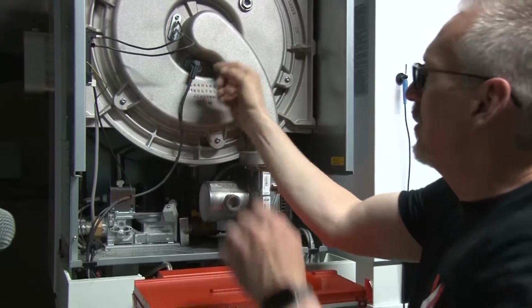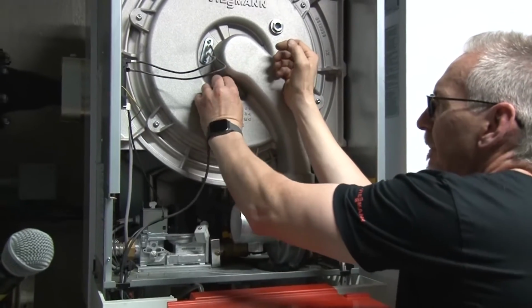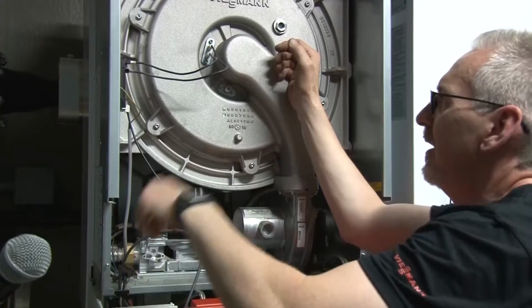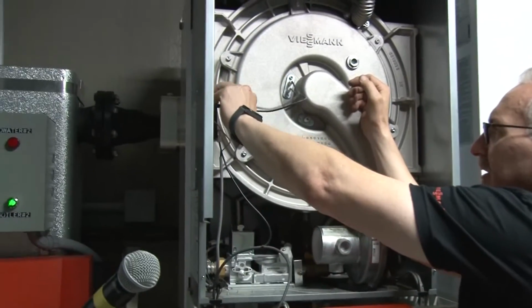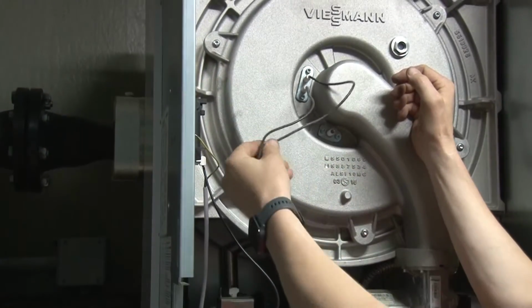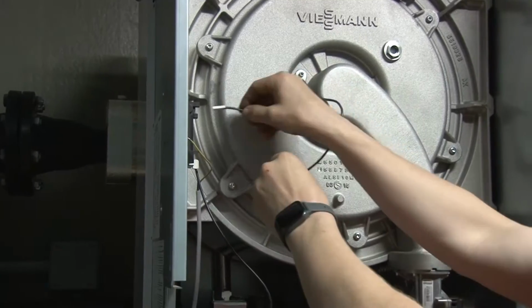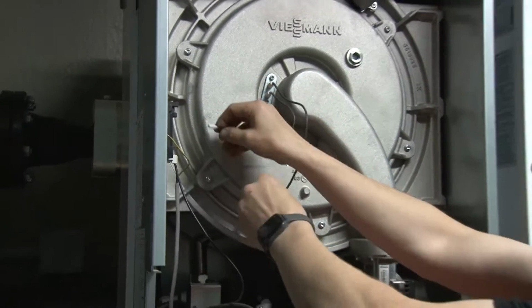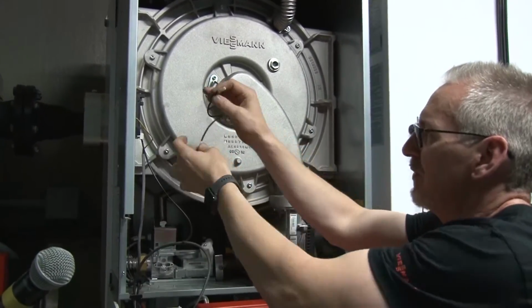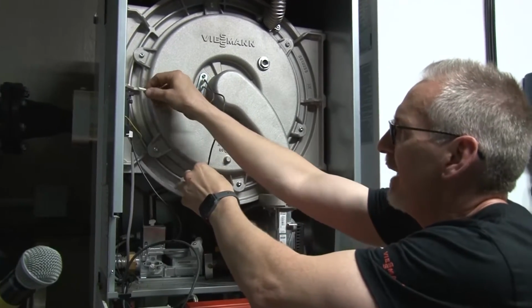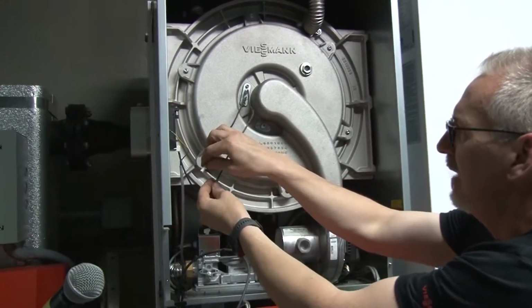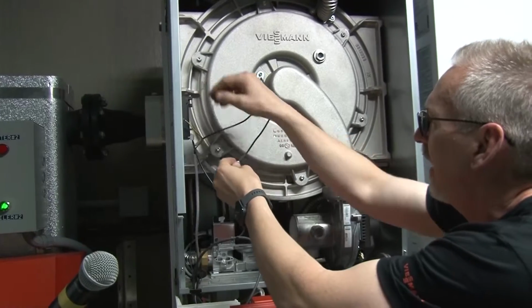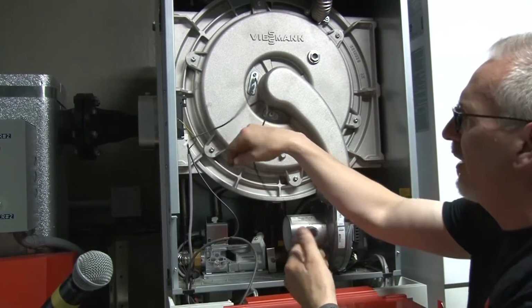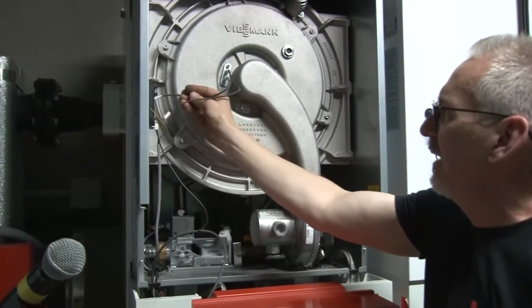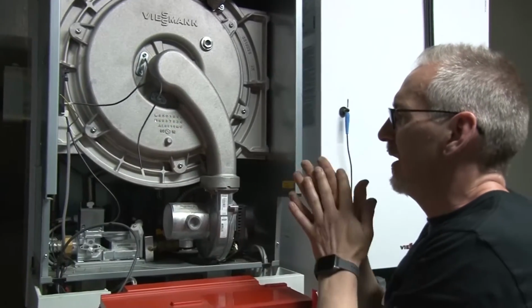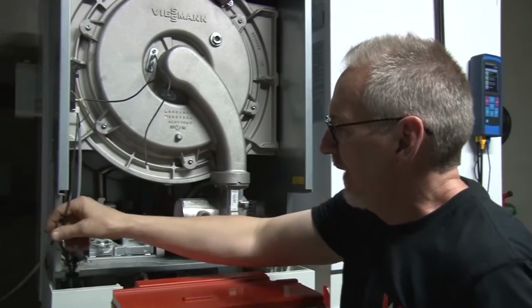I need to also remove my ionization electrode, and that's sitting right here, as well as the ignition electrodes. And the ignition electrodes, there really doesn't matter which way you put these back in. So if you forget which is the lower one and which is the upper one, there's no polarity on these. It's just based on the length of the cable. So typically the shorter one goes in the top, longer one goes in the bottom there, but it's just about the stress of the cable depending on where they're sitting. So you can have a look at that. That's it for that side of it.